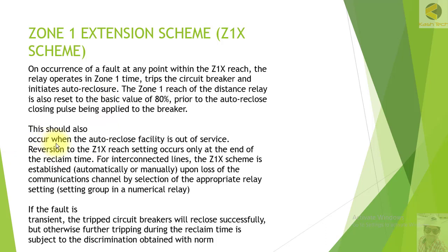This reversion could also occur when the auto-reclose facility is out of service; reversion to Z1X reach setting occurs only at the end of the reclaim time. For interconnected lines, Z1X is established automatically or manually upon loss of the communication channel by selection of an appropriate relay setting group in a numerical relay. It is possible that a permissive overreach transfer trip scheme is used when the channel is healthy, and when the channel fails we can select the Z1X extension scheme — this is the available facility for fast tripping when communication has failed.